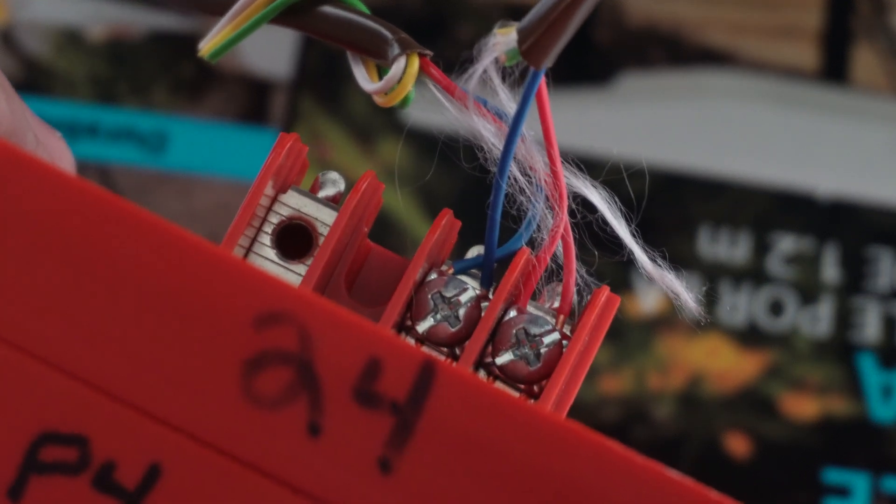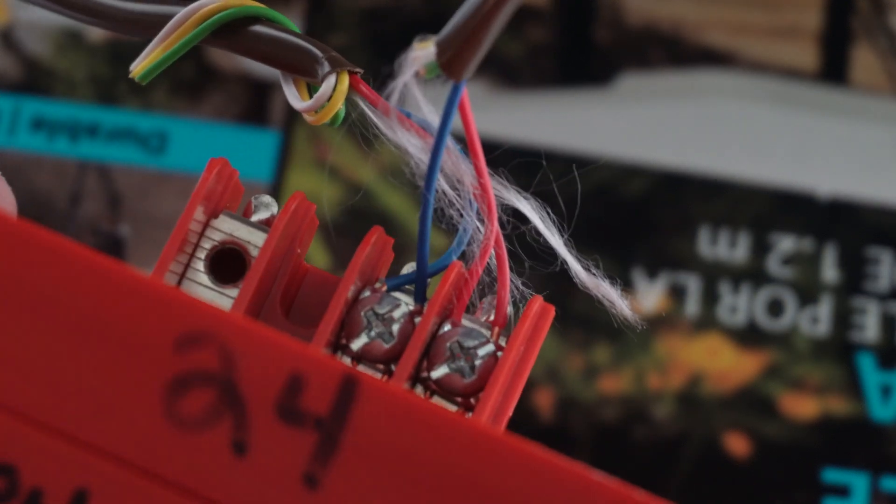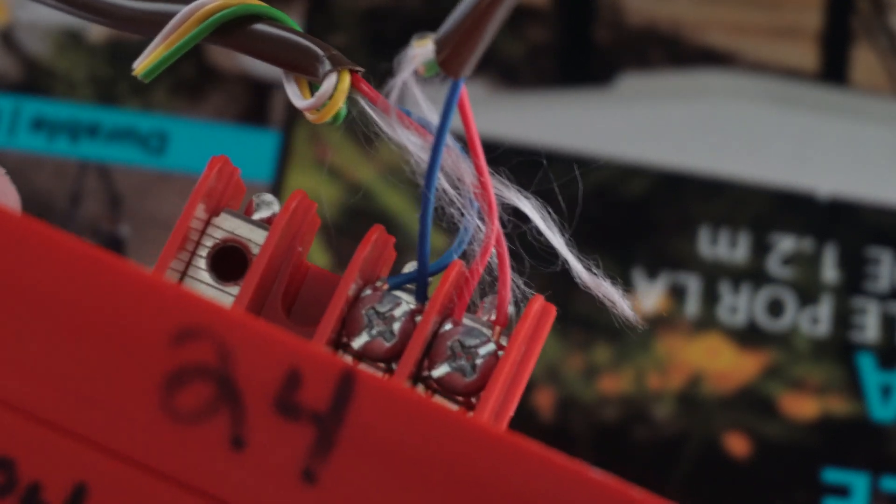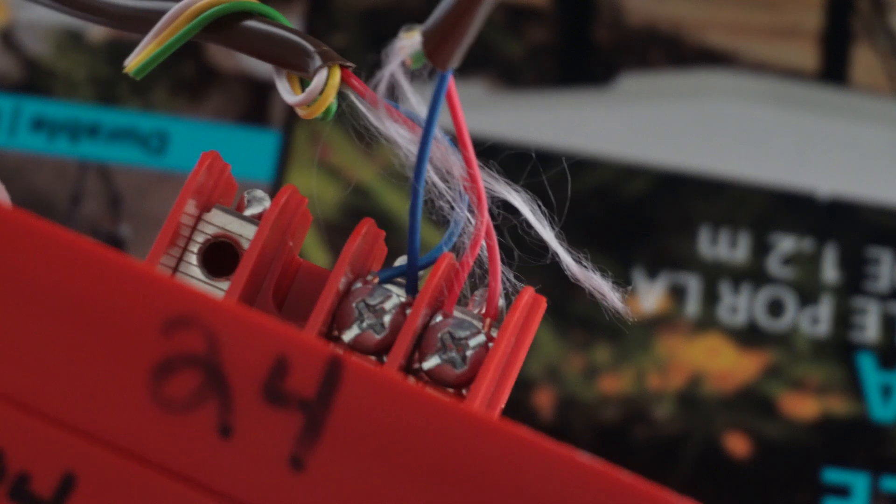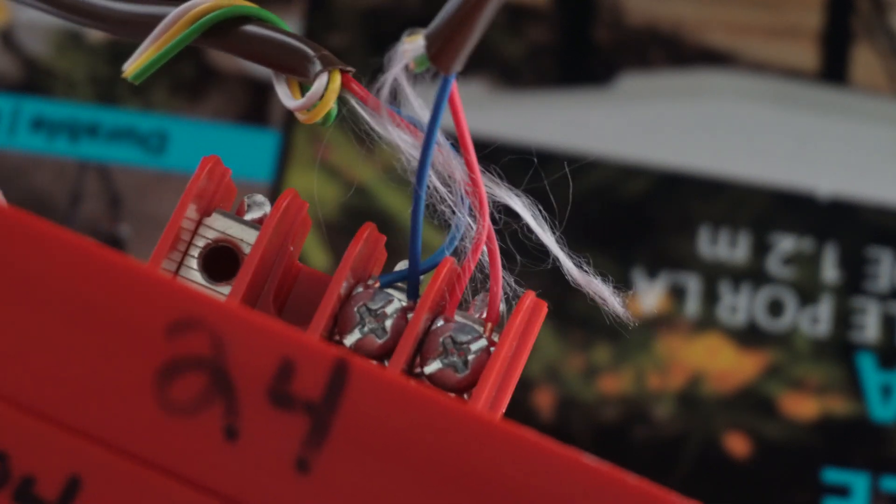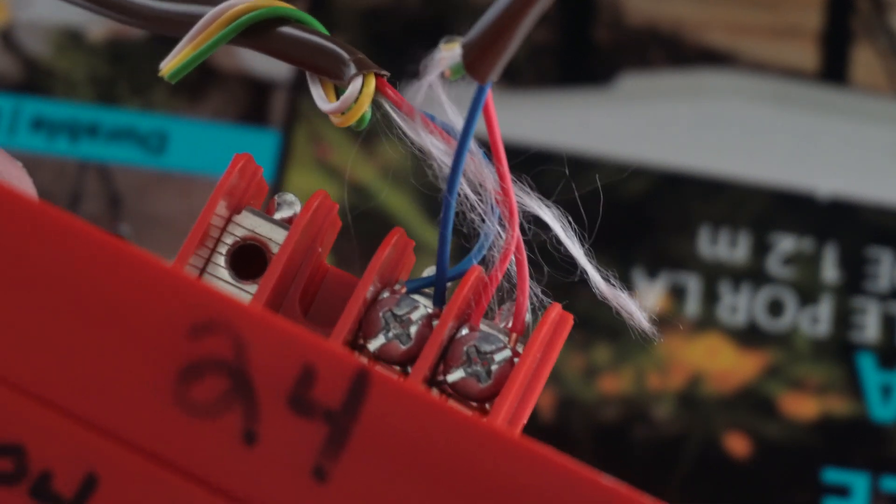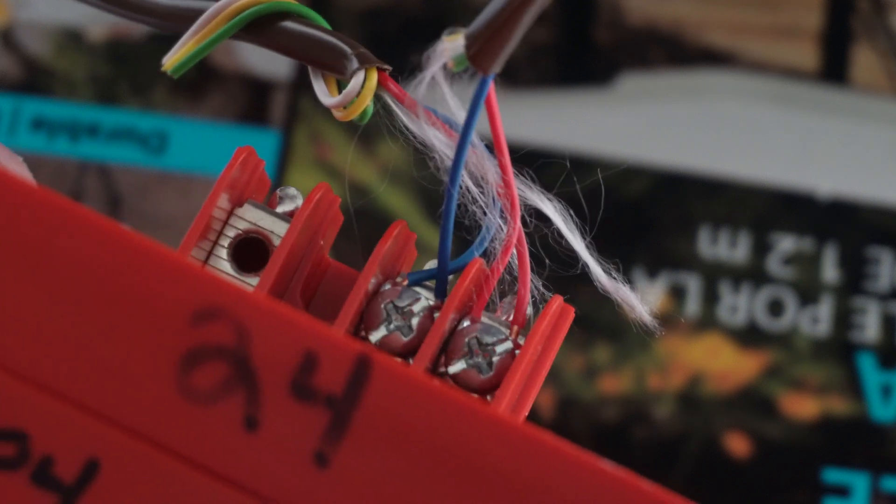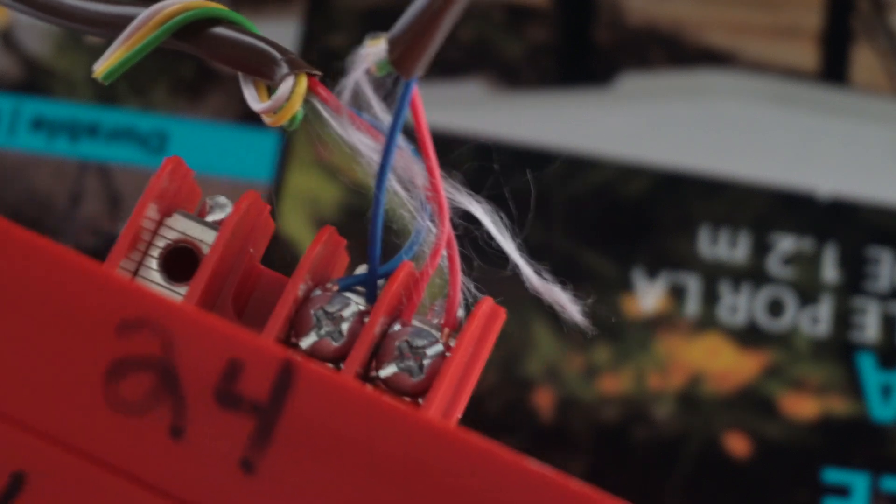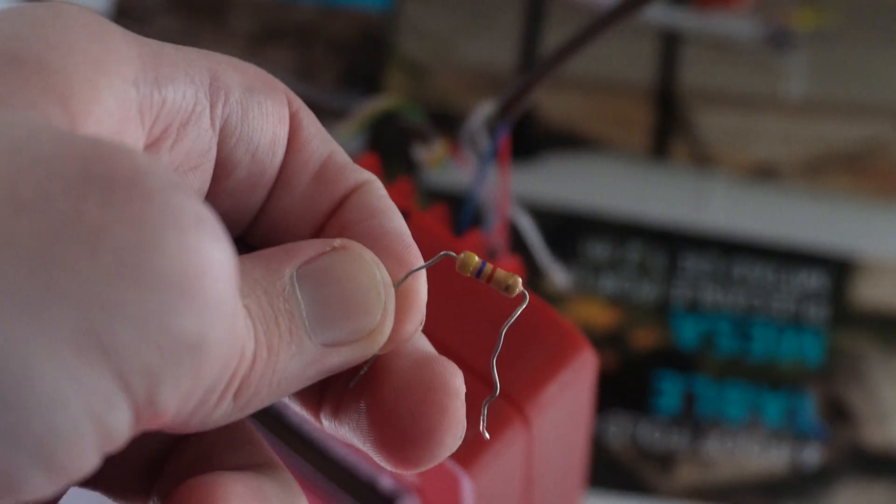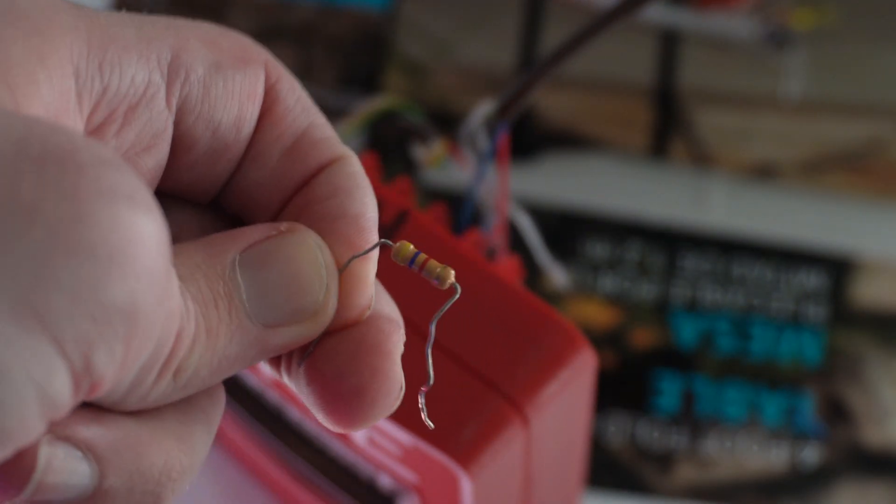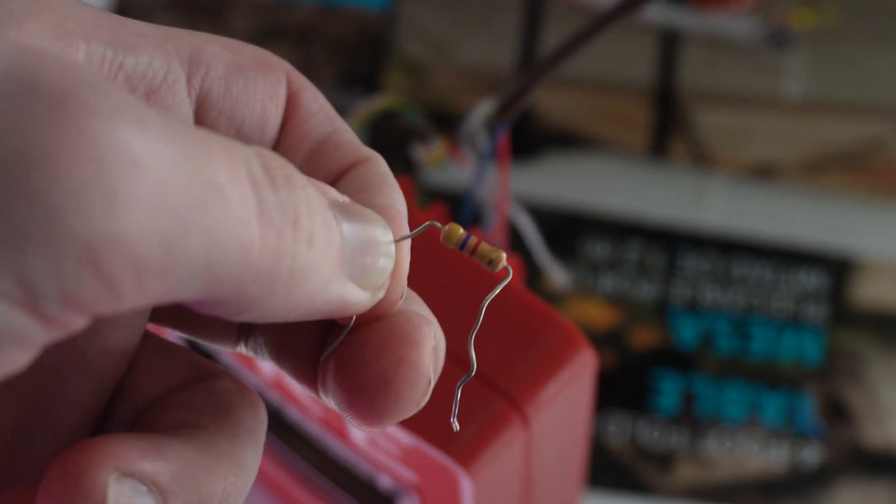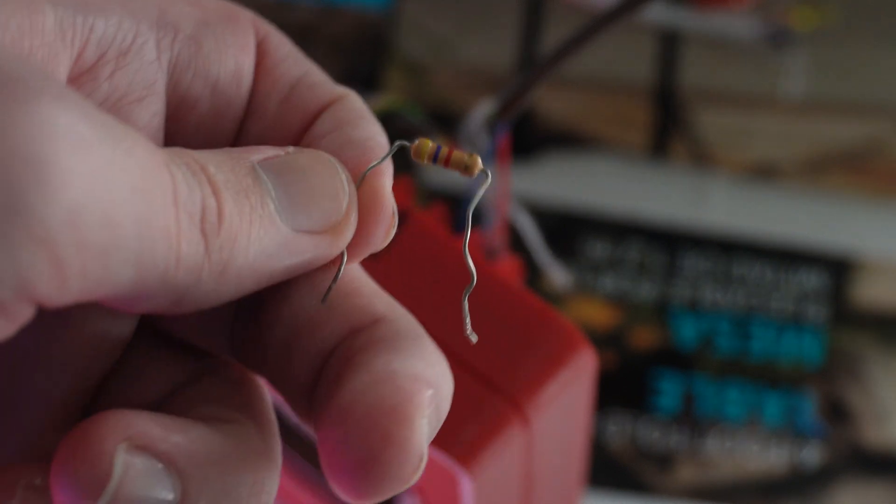Here is the pull station wiring now. The wire going to the smoke is just going to daisy chain right off the same positive and negative terminals from the previous device, in this case the pull station. The end of line resistor is getting moved to the smoke detector once we finish wiring that up.